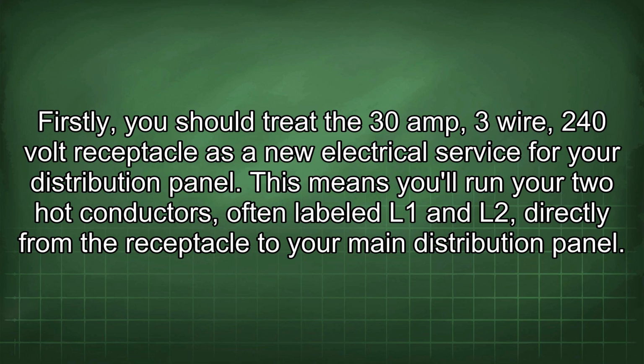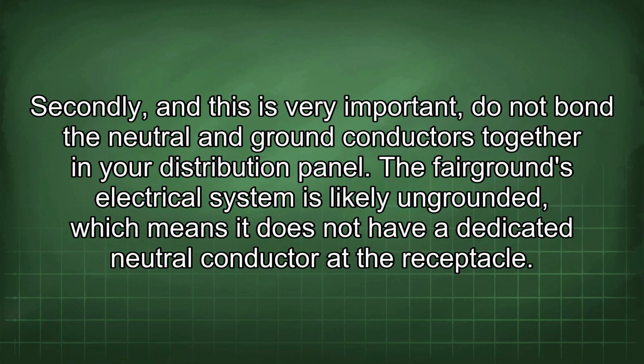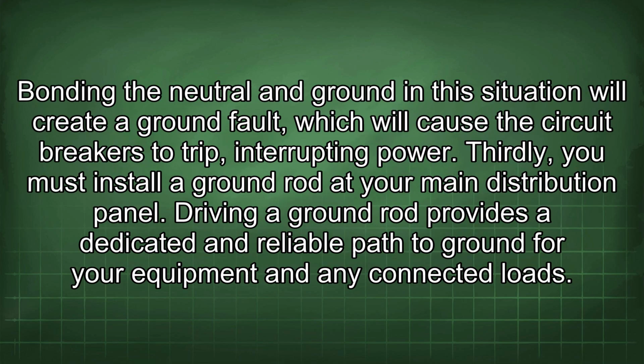This means you'll run your two hot conductors, often labeled L1 and L2, directly from the receptacle to your main distribution panel. Secondly, and this is very important, do not bond the neutral and ground conductors together in your distribution panel. The fairground's electrical system is likely ungrounded, which means it does not have a dedicated neutral conductor at the receptacle. Bonding the neutral and ground in this situation will create a ground fault, which will cause the circuit breakers to trip, interrupting power. Thirdly, you must install a ground rod at your main distribution panel.